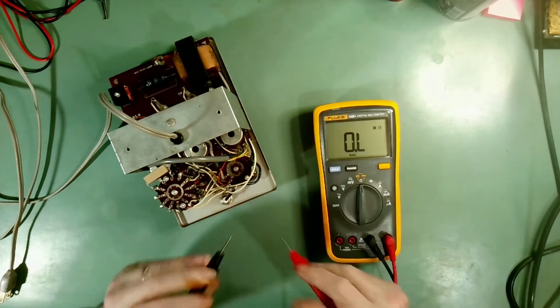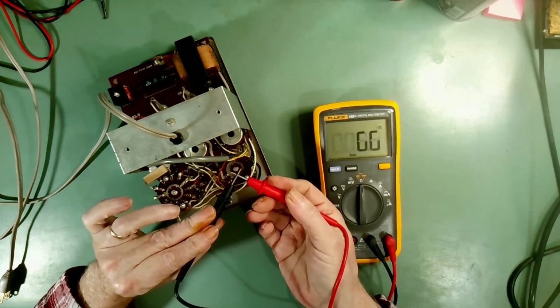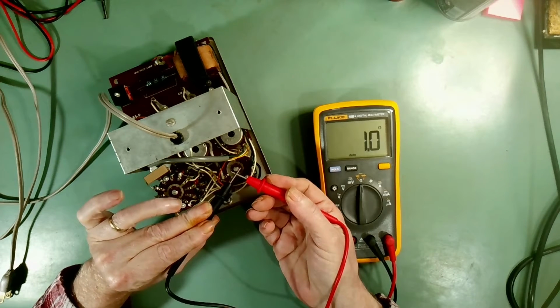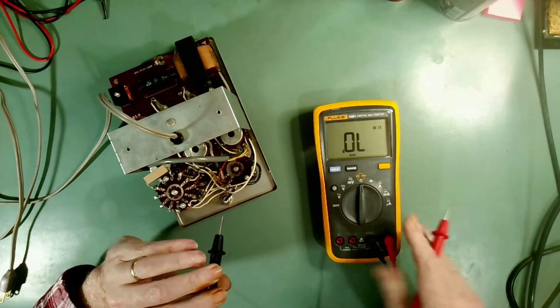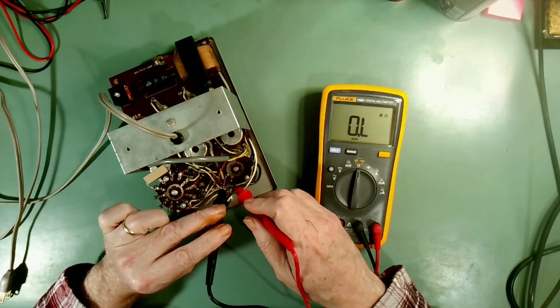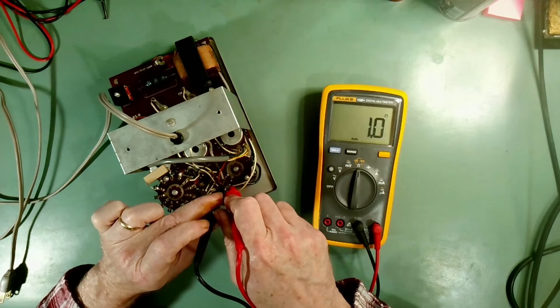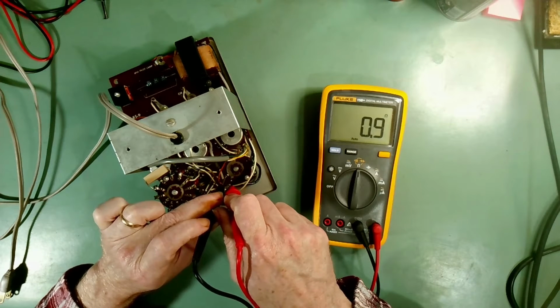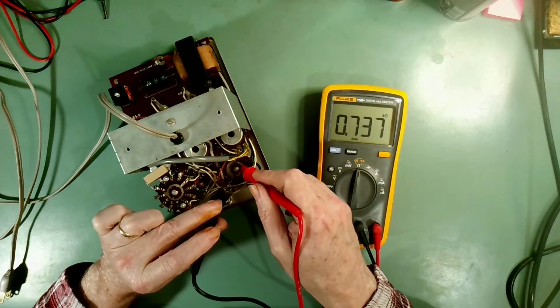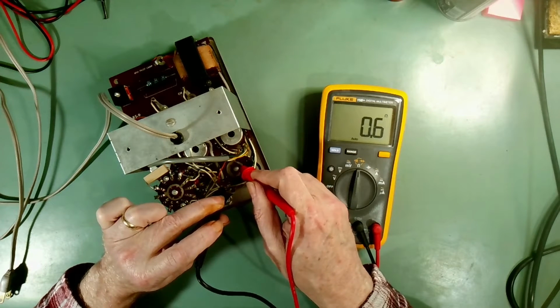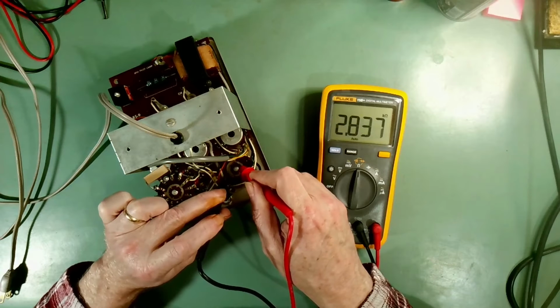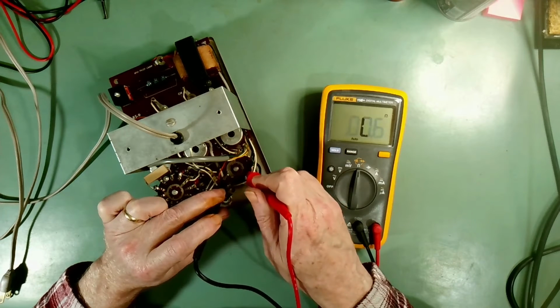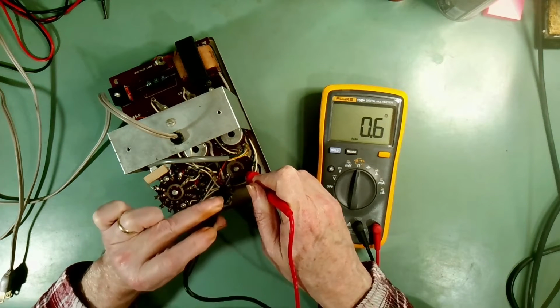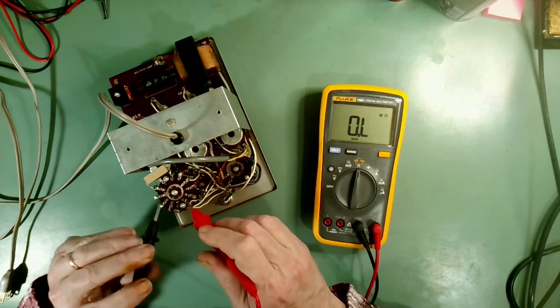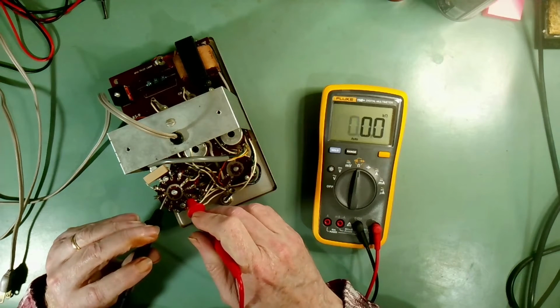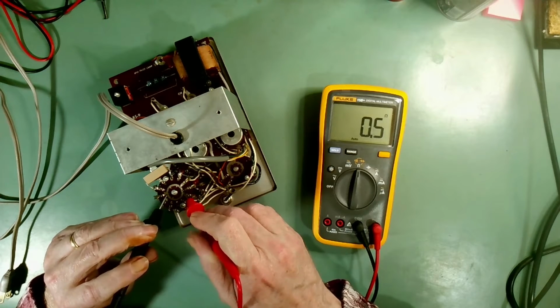But to show you what's going on with the cleaning, if you look at the meter here, it's registering around 1 ohm for the lead resistance. And if I just go here and connect to those two, the unit is on. It's showing 0 ohms. So no matter where I click it on here, it's going down to 0.6. Go move it over here. No matter where I put my probe, this here is showing perfect continuity, and the same for up here as well. So Tarn-X did a great job.